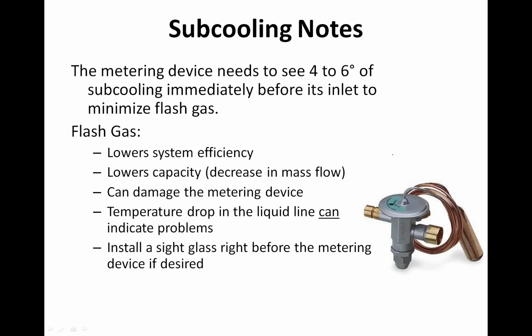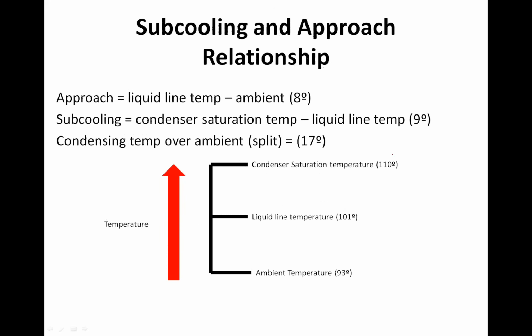But the reason that I like to install a sight glass before the TXV is simply to make sure that the refrigerant's dry, right? Because usually it has a moisture indicator that turns green when you have dry refrigerant in there. Not so much to see if there's 100% liquid in there, although you can do that, but to indicate the refrigerant's dry before it enters the metering device.